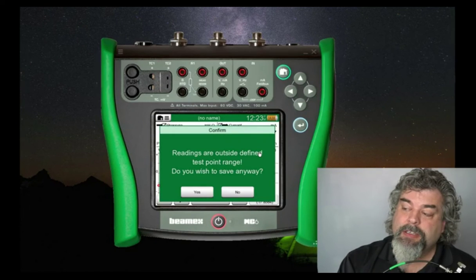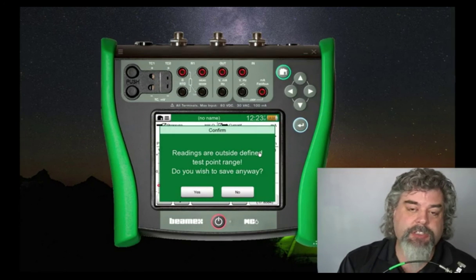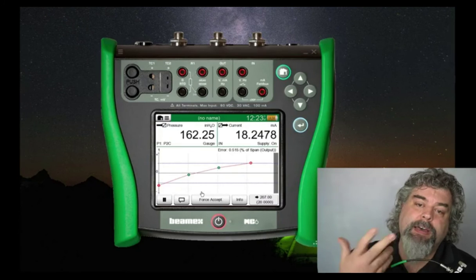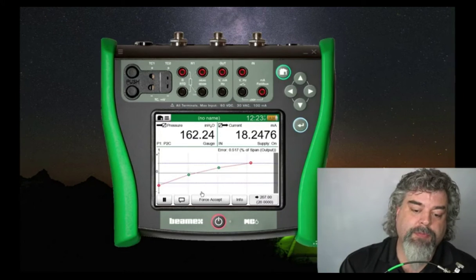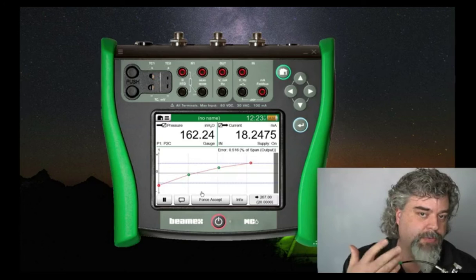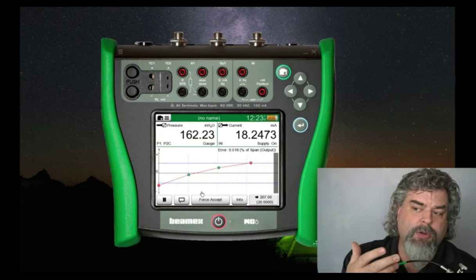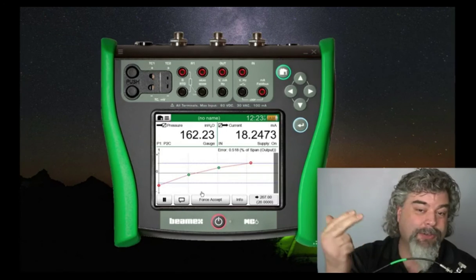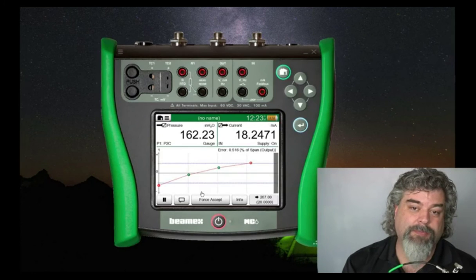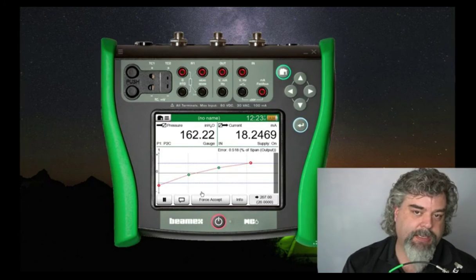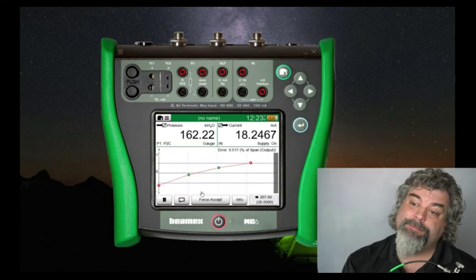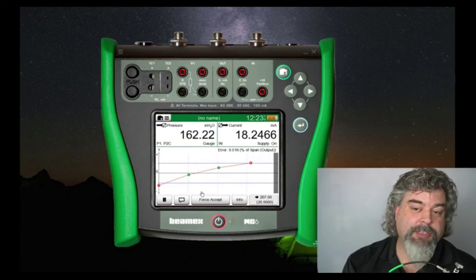This also is a good example if your final test point is a pressure that you cannot simply achieve with the pressure pump that you have. Or maybe you have a vacuum and you can't go low enough. You can't hit absolute zero. Well, there's not much that can outside of a space laboratory. There's a couple options, but then they start counting actual air molecules.